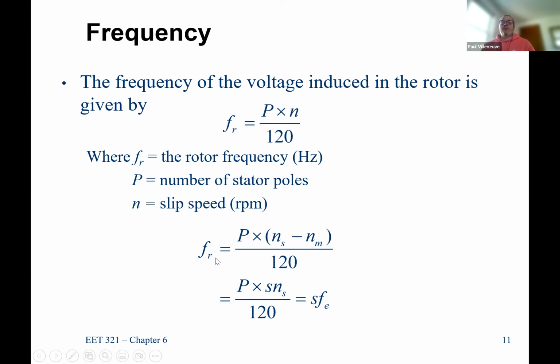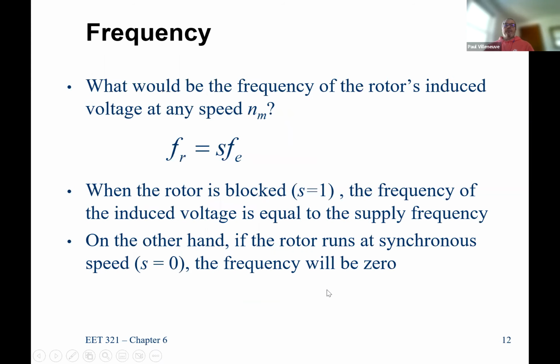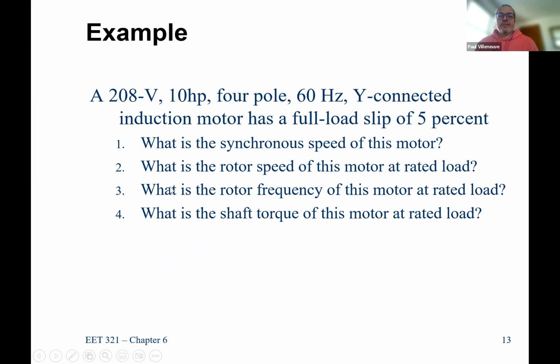So it's very common for rotor frequencies to be 1, 2, or 3 hertz. So that's the actual AC waveform. That's the actual frequency on the rotor as compared to the 60 hertz on the stator. Okay. So it's very important to understand that these frequencies should never be the same if you're going to get operation. The most you're ever going to get is 60 hertz. The least you're ever going to get is maybe half a hertz if it's still going to operate as a motor. Okay. So what would be the frequency of the rotor's voltage? Excuse me. How do we vary this? Then again, it's going to vary from 60 hertz to 0 hertz. Okay. All right.